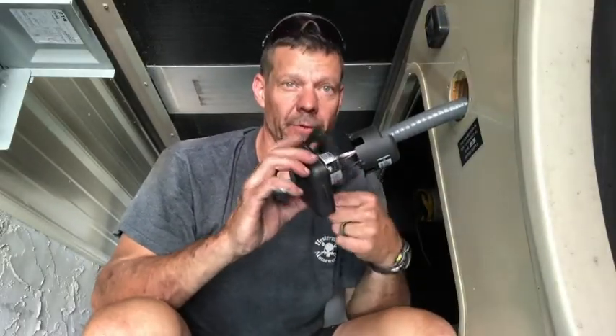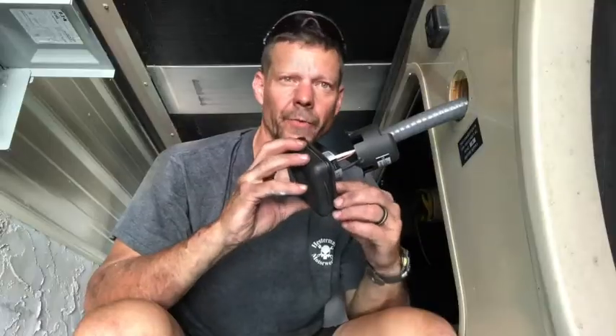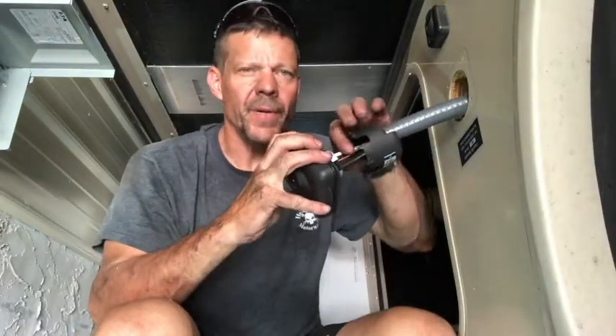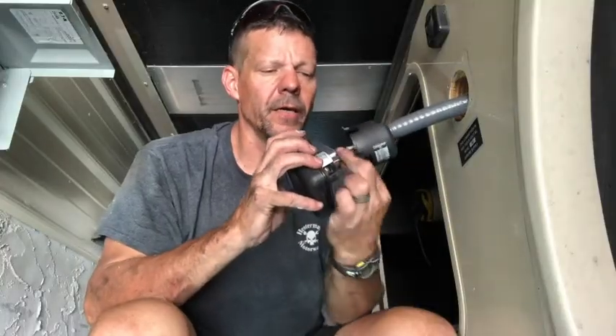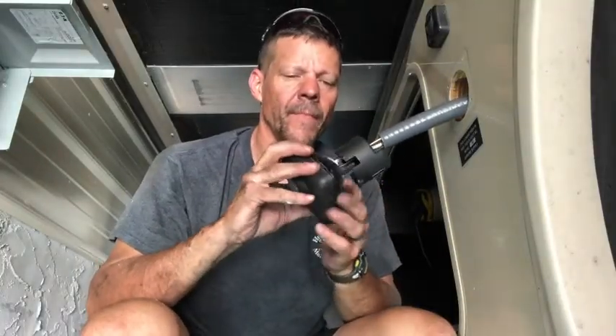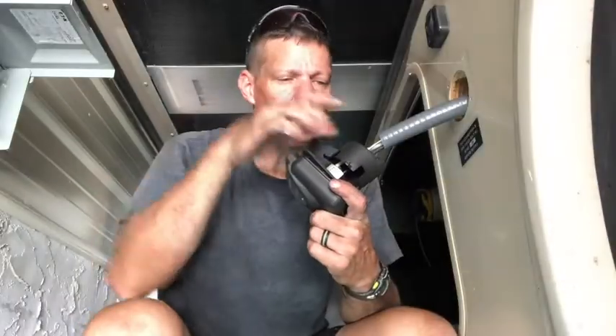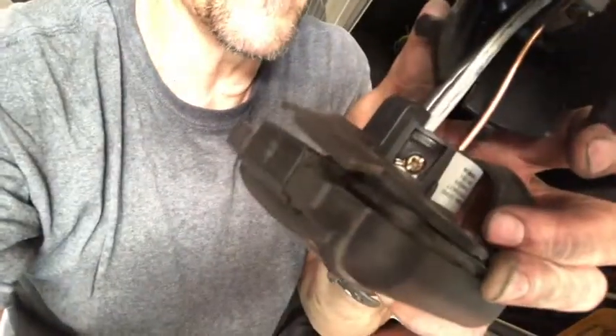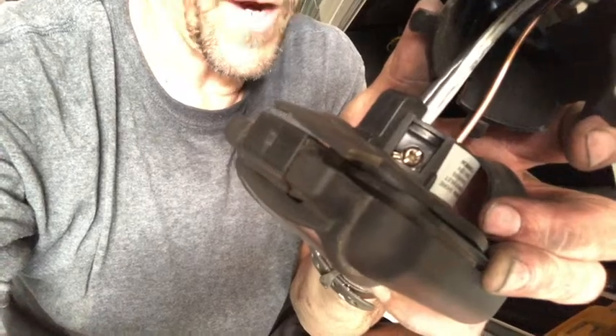So even though this wasn't the problem, we double-checked, and it could be on your rig as you're troubleshooting. Basically I'm going to give each of those wires a tug and make sure it's secure. If it's not secure, make sure the wire's going all the way into the fitting, then tighten those screws down. There's a little clamp screw right there for each wire - there's 3 of them.